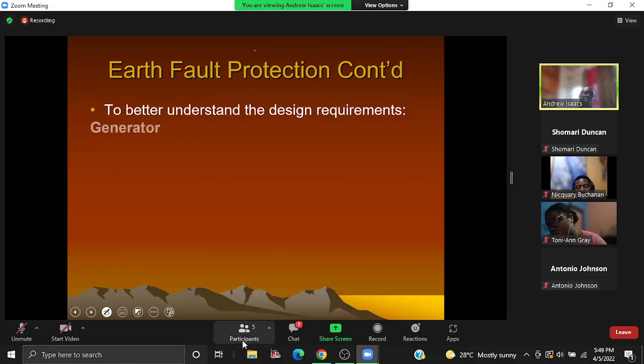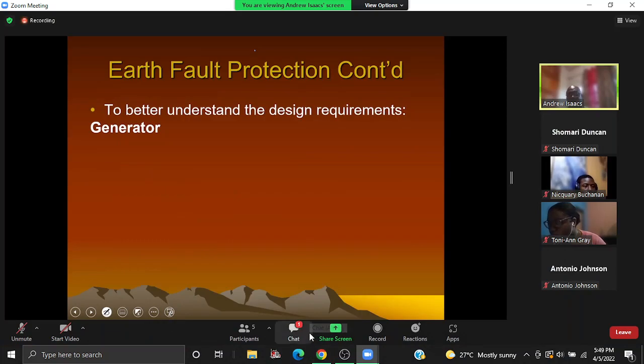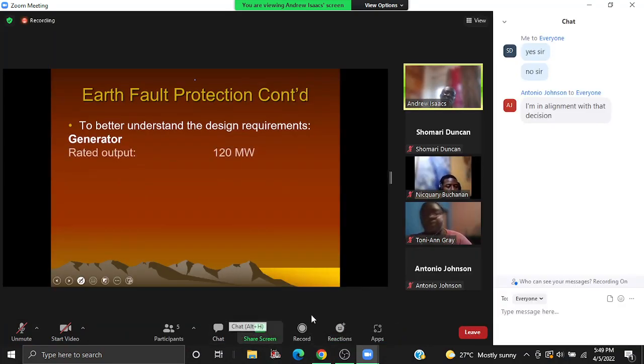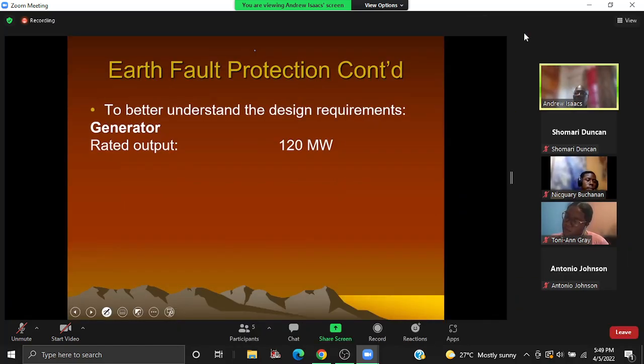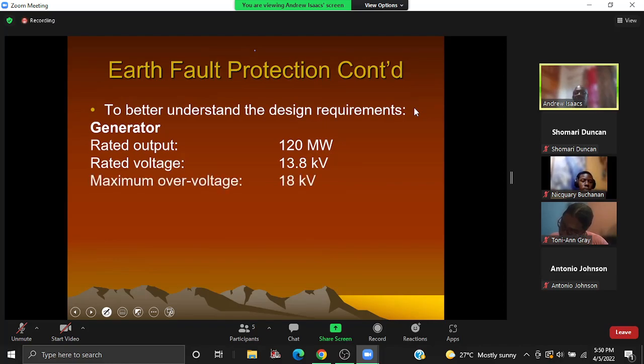All right, so here are the requirements. This is what I'm protecting. We have a generator rated output 120 megawatts. We have no such in Jamaica, but you know, we have 120 megawatts. Terminal voltage 13.8k. Maximum over voltage 18k. And note that 18k would be approximately 1.3 times the 13.8.